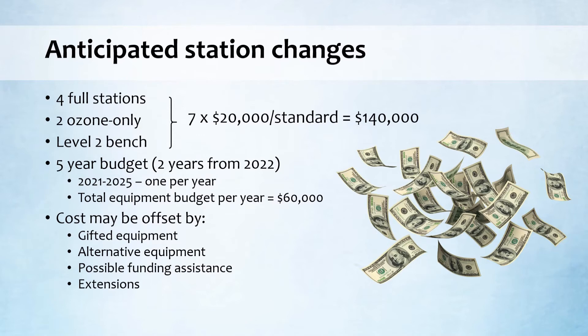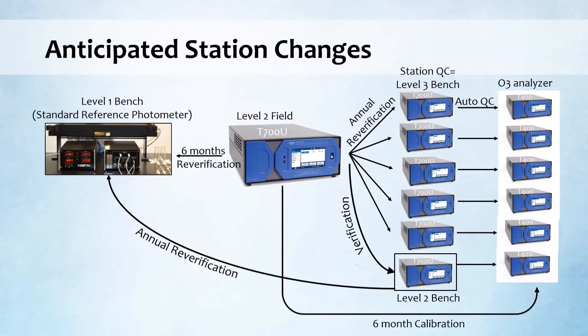Here's what we're thinking across our stations. We replace all of our QC instruments with the T700U. Then at our main headquarters — our cleanest station — we take that T700U and send it back for annual re-verification against the level one bench, which would make it a level two bench. We can use that for the initial verification of the rest of the station T700Us. Then everything else would be pretty much the same — our field transfer standard gets sent back on a six-month verification, used to perform the six-month calibration of the ozone analyzer, and then the annual re-verification of the station QC instruments.